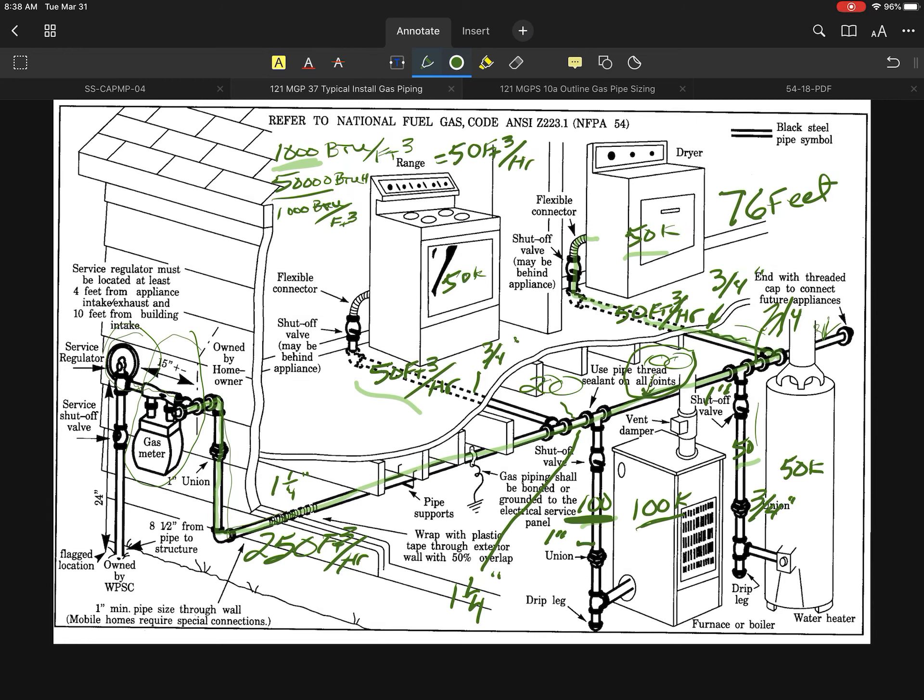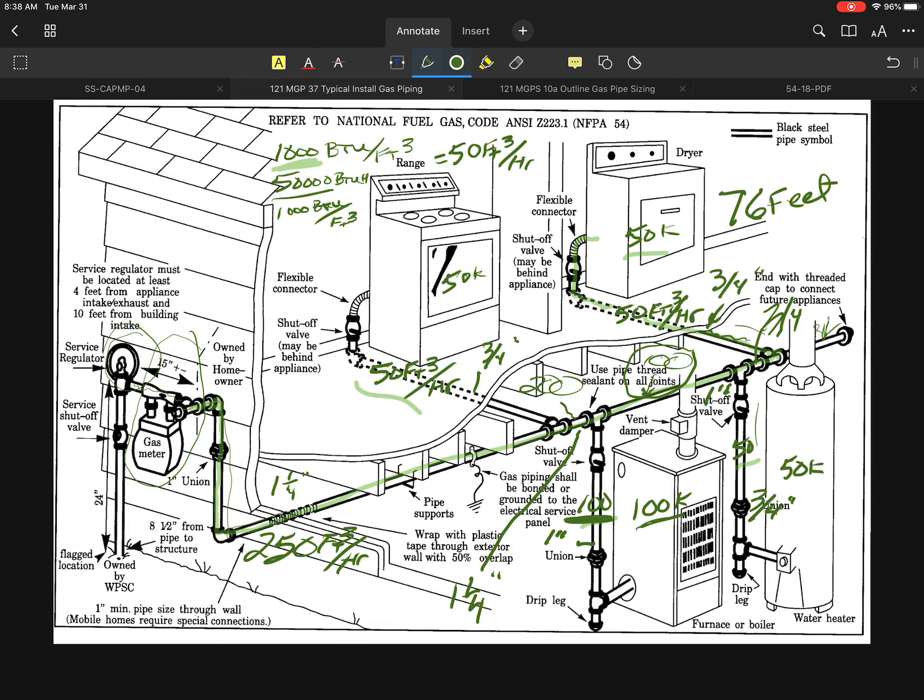You might be wondering, what if my appliance happens to have a half inch inlet or a 3/4 inch inlet? In the case of this boiler, there's a very likely chance that it might have anywhere from a half inch to a 3/4 inch inlet, and it's got a 1 inch pipe going into it. What you primarily do is bring the 1 inch as far as you can, and then you just reduce right at the gas valve or just prior to the gas valve. That's typically how that's handled. So that's a little bit of the longest length piping method.